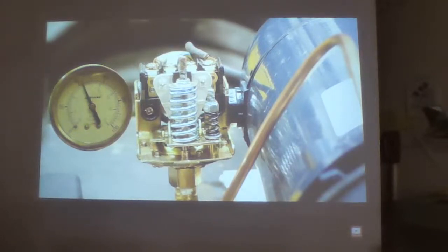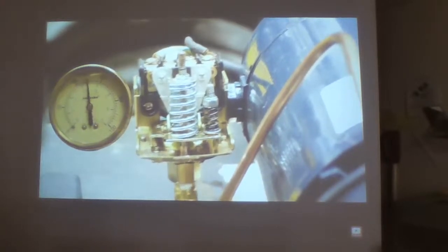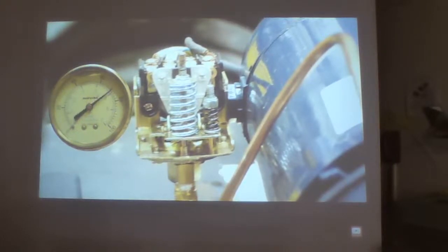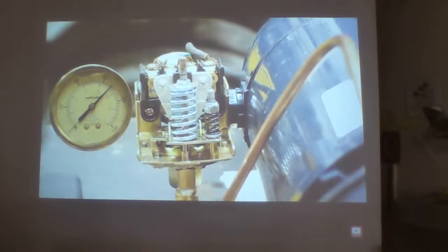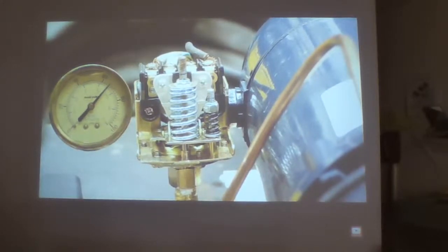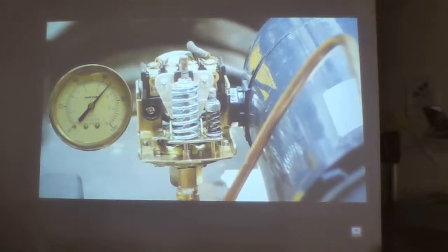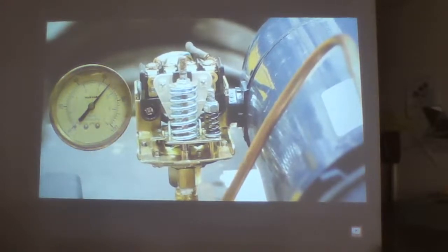So the pressure's falling, and we're about 40 PSI. The pump continues to build pressure, and about 66 actually. So that was about, what was that, 3.5 turns, or 3 turns, I believe, that I did on that one. So 3 turns upped it about 5, 6 PSI. So it's almost 2 PSI per turn.